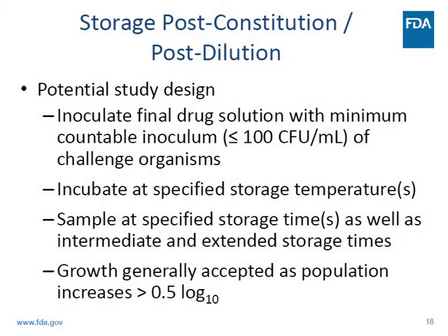You would then incubate that inoculated solution at the storage temperatures specified in the package insert. Then you would sample at the specified storage times, as well as at intermediate and extended storage times. We'd like to see if you can observe a growth trend during that time period.